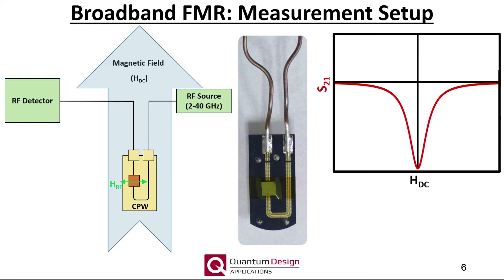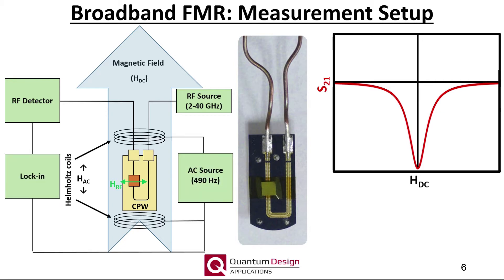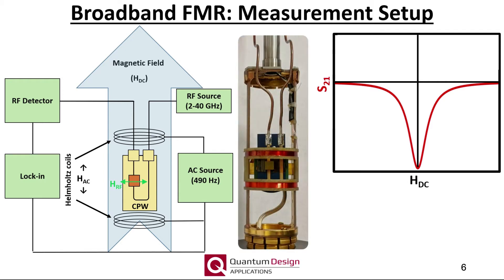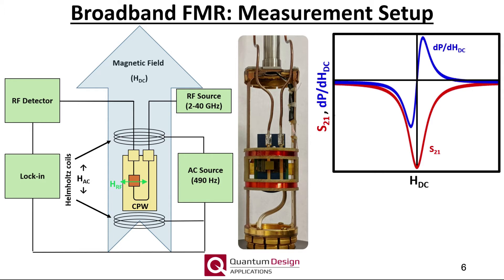Ideally, the sample should be placed here, as also shown in this picture. The RF field will be oriented horizontally, which is important as the DC magnetic field provided by the superconducting solenoid in the PPMS is vertical. Remember, in order to resonantly excite the magnetic moment, the RF field must be perpendicular to the DC field. For our purposes here, the RF frequency will remain fixed and the DC magnetic field is swept. At a particular combination of DC field and RF frequency, the sample magnetic moment will precessionally resonate. During resonance, the sample will therefore absorb some of the RF power, which will therefore not make its way to the RF diode, resulting in a dip in the transmitted power. For those of you familiar with the Vector Network Analyzer, this is analogous to an S21 measurement and is essentially just the DC voltage on the RF diode in our example.